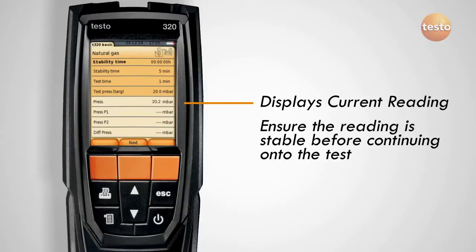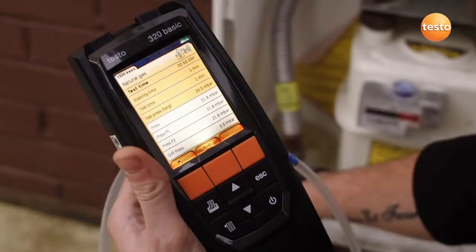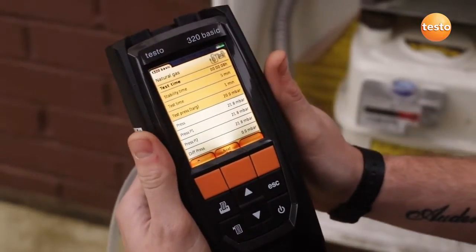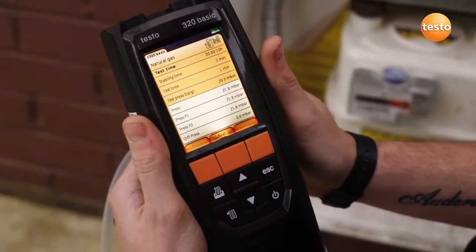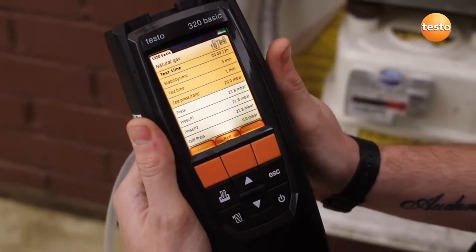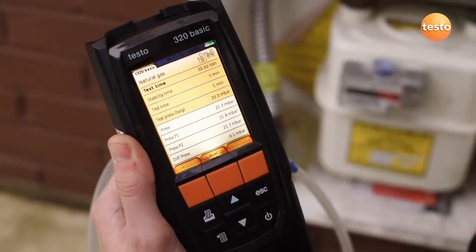Industry standards originally formulated for carrying out the tightness test with a U gauge state there should be no discernible pressure drop during the tightness test. Using a flue gas analyzer or digital manometer, the maximum pressure deviation is 0.2 millibars, which is the value the industry accepts as a discernible drop. At the end of the test time, the results are automatically logged.